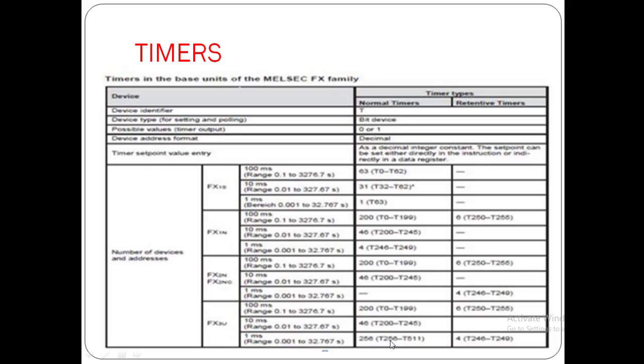A 1ms timer is also available in FX3U — 4 retentive timers and 256 non-retentive or normal timers. Different timers are available in different PLC series; it may be retentive timer or non-retentive timer. Retentive timers are those which retain their time value when they are turned off. Non-retentive or normal timers are those which cannot retain their time when turned off — when restarted, they start from 0 again.